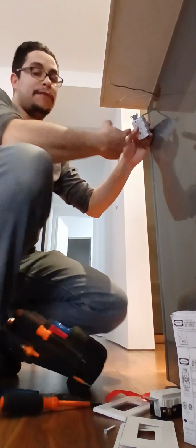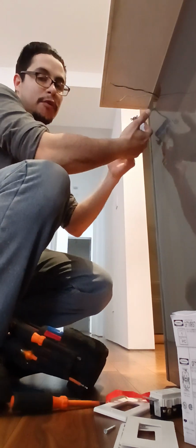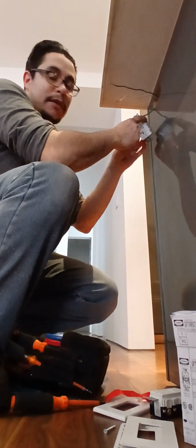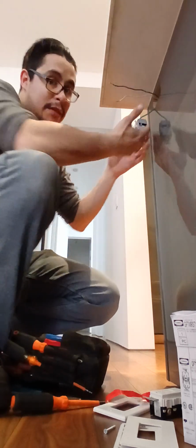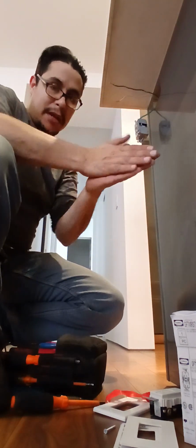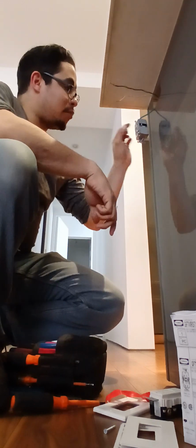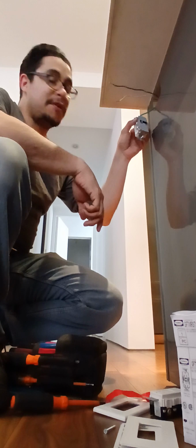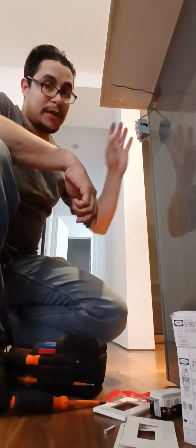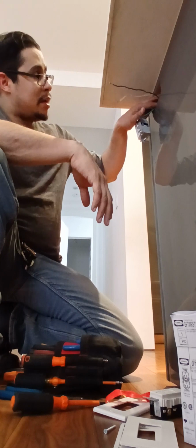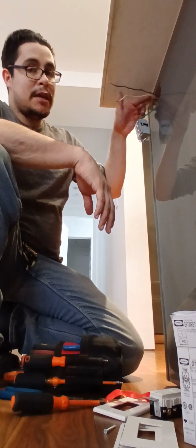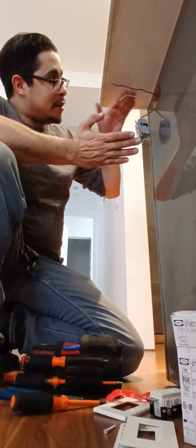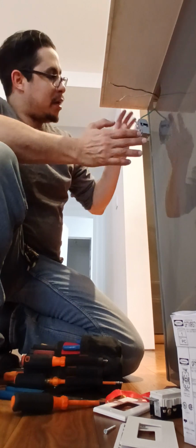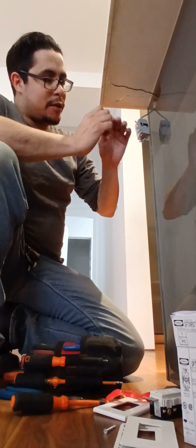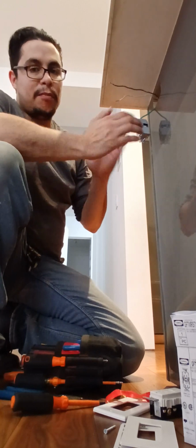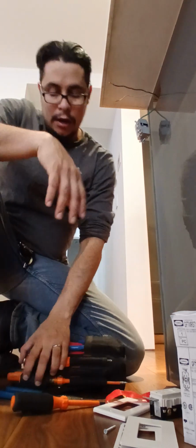You back wire these devices. You could do side wiring or looping, but back wiring is strongly recommended. If you see these, it's designed to be back wired and there's nothing wrong with that. There's a clamp that clamps onto it really well. Don't make hooks on these because it becomes very difficult to tuck the wire and the device back in. In some cases, if you have a tight cut-in box like this, these boxes kind of warp or bow in a little bit, and if you shove it in with hooks or loops and there's tape on it, it may mar the tape to the point it exposes the wire, and then you can have an arc and a ground fault.